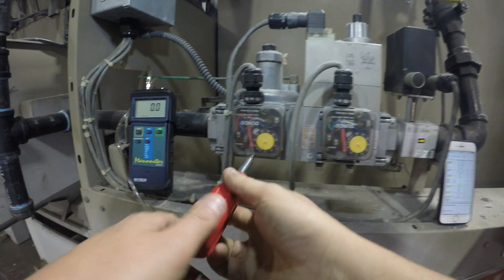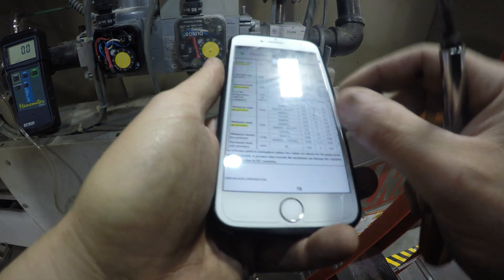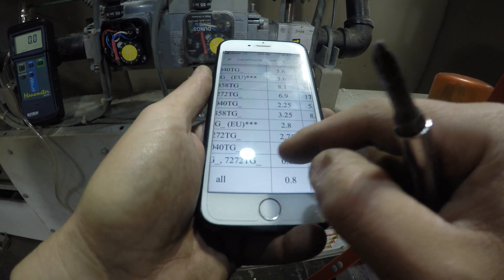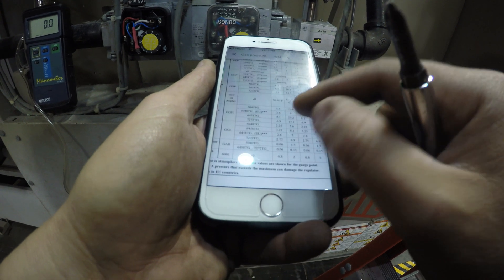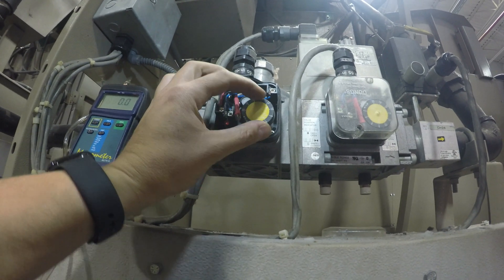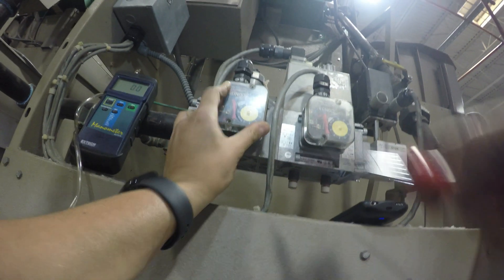Now we're going to take a look at the book and check the minimal gas pressure setting. The gas pressure coming into the dryer is 13.5, and the low gas pressure setting in the book for a 6458 Milnor dryer should be 3.25. Currently it's set at about 4, so we're going to turn the knob down to 3.25. There's a little arrow on the bottom — just line up the number with the arrow, then put the cover back on.